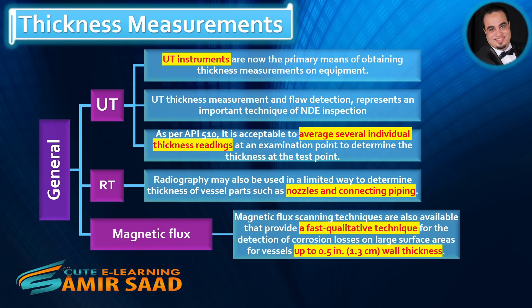Magnetic flux scanning techniques are also available that provide a fast qualitative technique for the detection of corrosion losses on large surface areas, for vessels up to 0.5 in (1.3 cm) wall thickness.